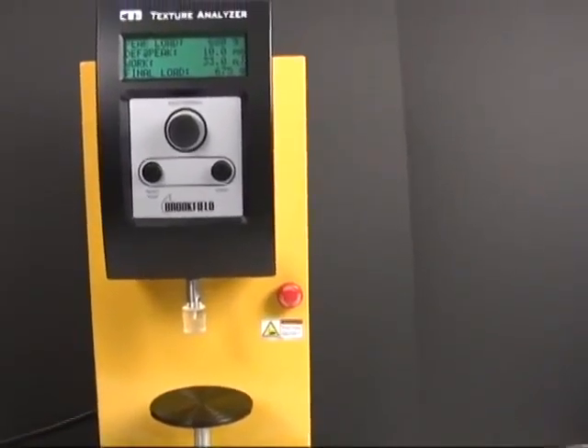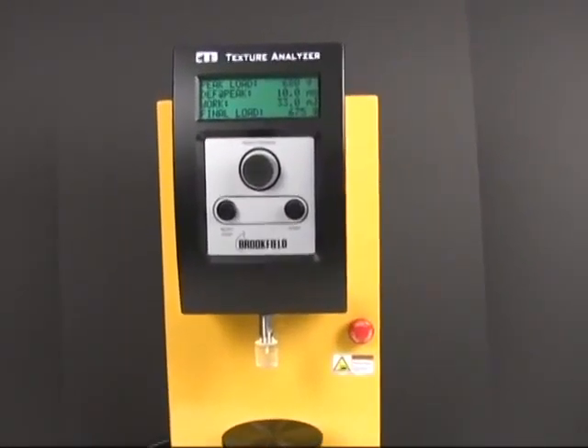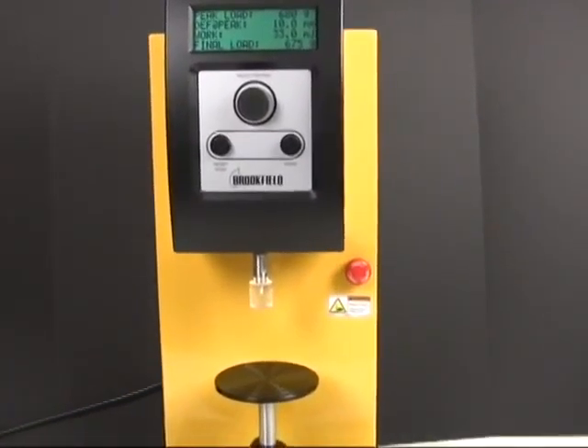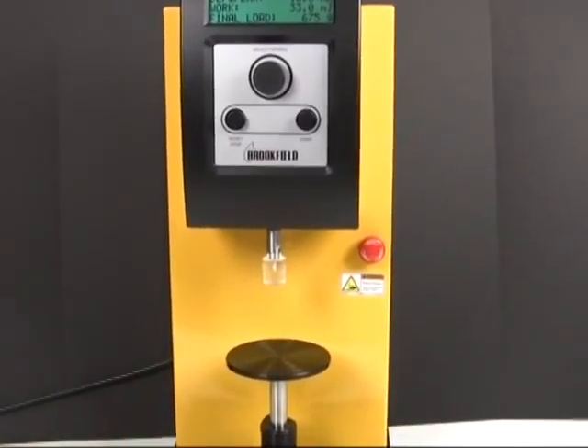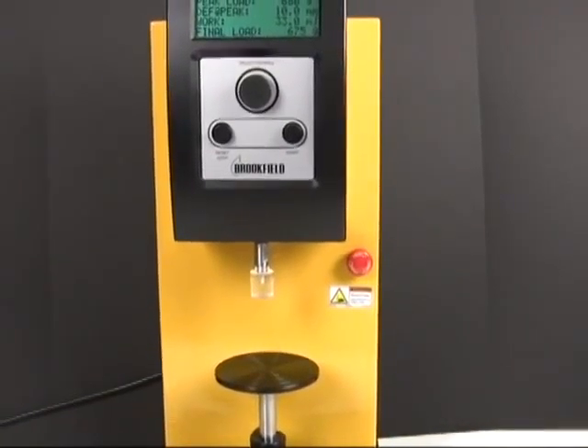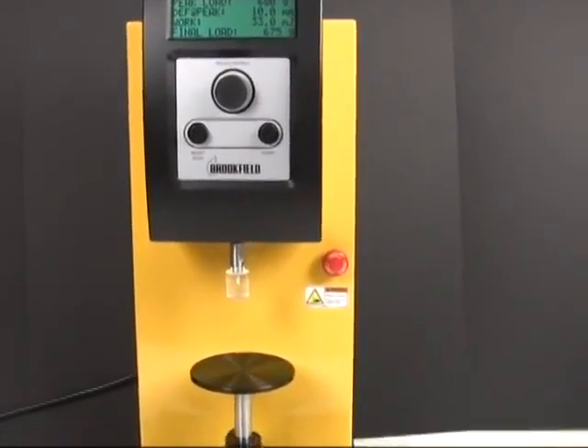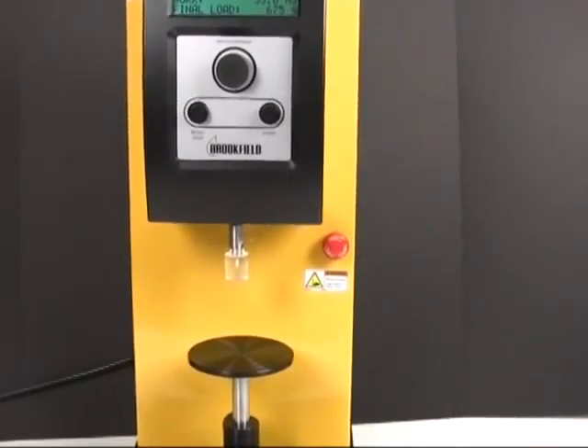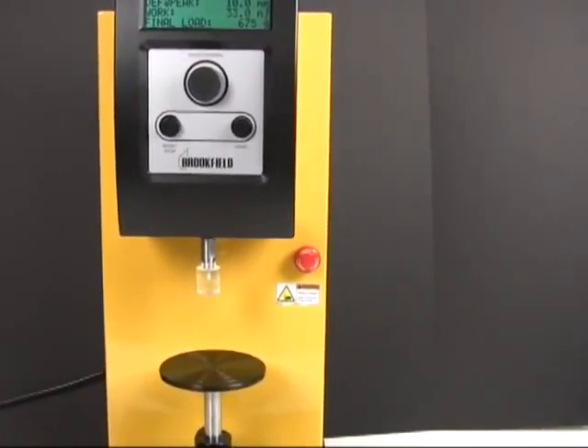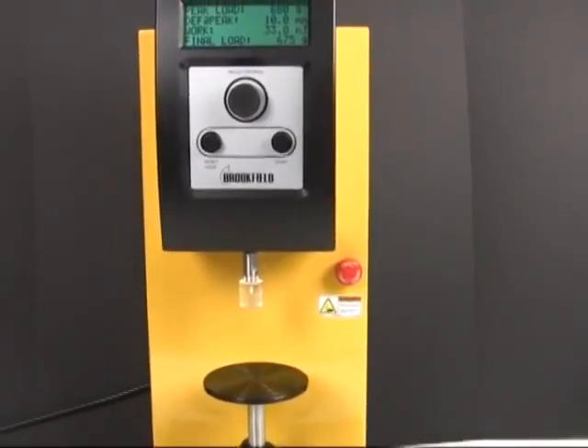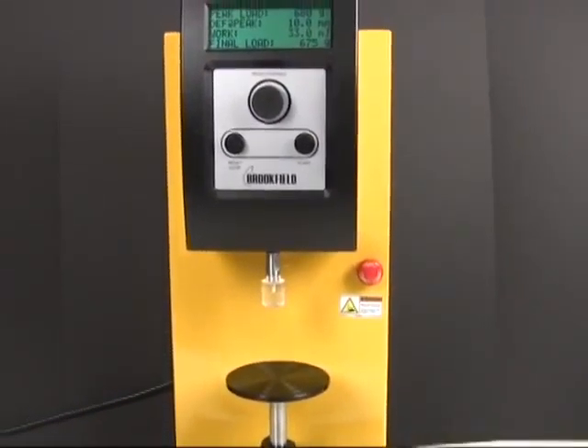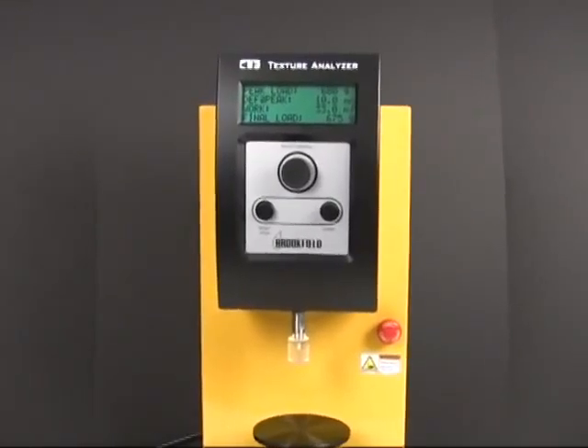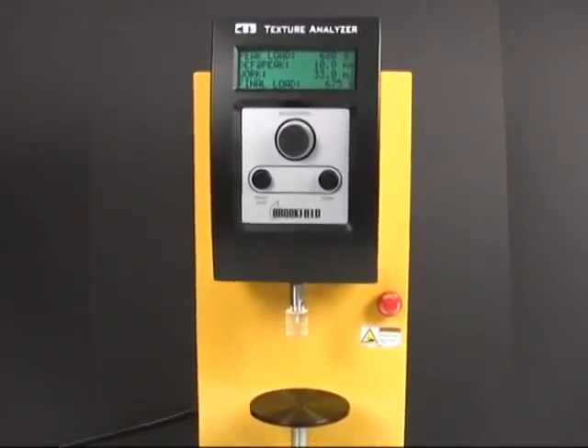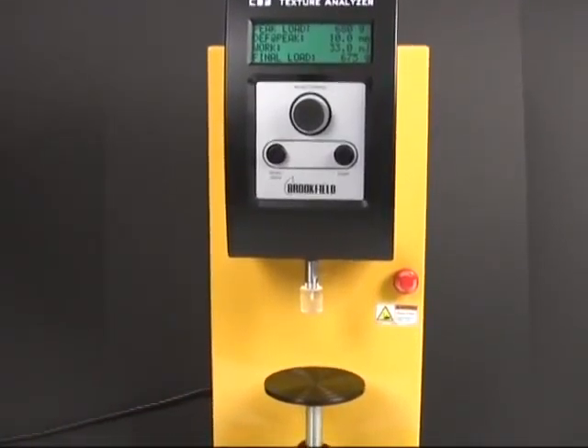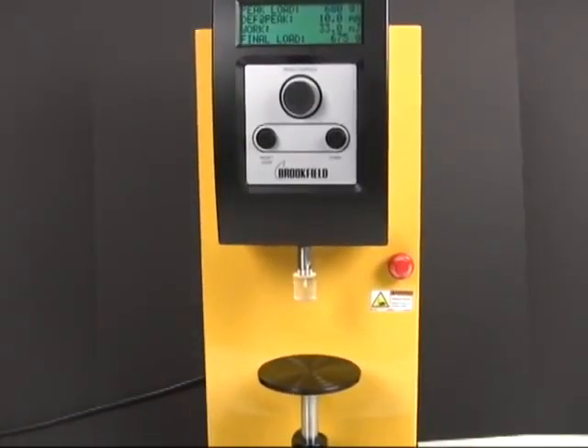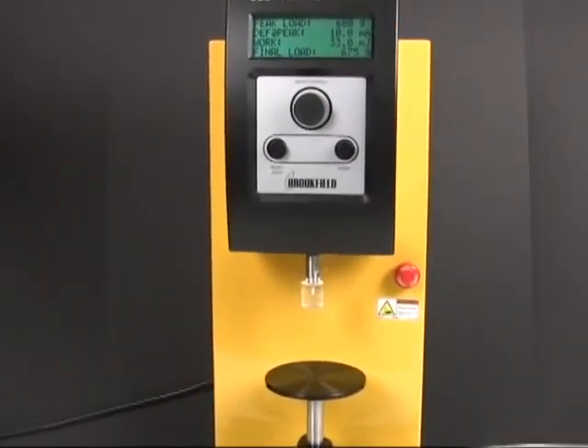You can't store positions, which tends to be a huge issue for testing items like gels and anything in a container. You can't maintain a target force, which makes it pretty much useless for anybody dealing with adhesives, medical adhesives. The small travel range, being 4 inches, and the distance between the probe and the back wall being 3, really limits the type and size of objects you can actually put in and test in the machine. Not being able to change the load cell in the instrument really limits the flexibility you have.